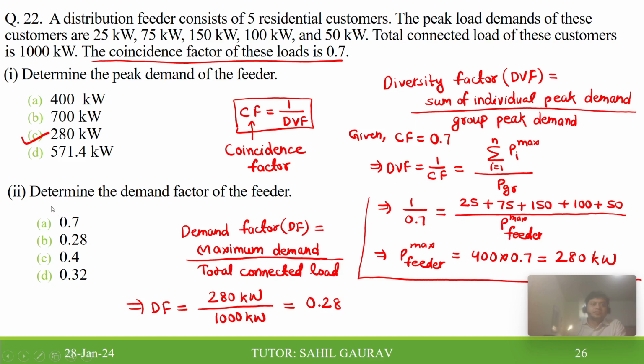Now in the second part, you have to calculate the demand factor of the feeder. Demand factor is nothing but, sorry, it is the ratio of maximum demand to the total connected load. We have calculated the maximum demand, that is the peak demand, in the previous part. The maximum demand is 280 kilowatt and the total connected load of these customers is given as 1000 kilowatt. So from there you can calculate the demand factor, and it comes to 0.28.